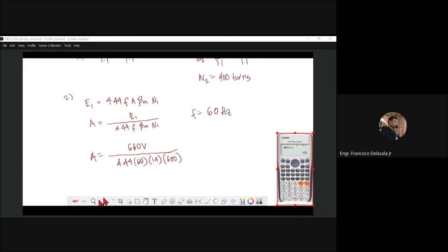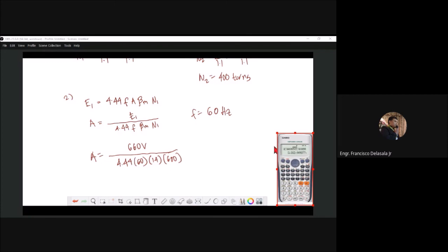Now we can solve for our area. We have 660 volts for our primary, over 4.44 times 60 Hz for frequency, times 1.4 Tesla for flux density, times 600 turns for the primary. Using the calculator: 660 over (4.44 × 60 × 1.4 × 600).